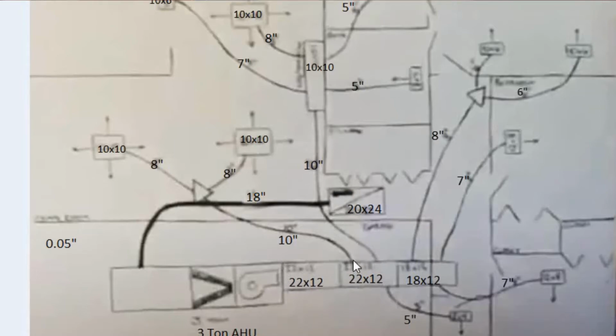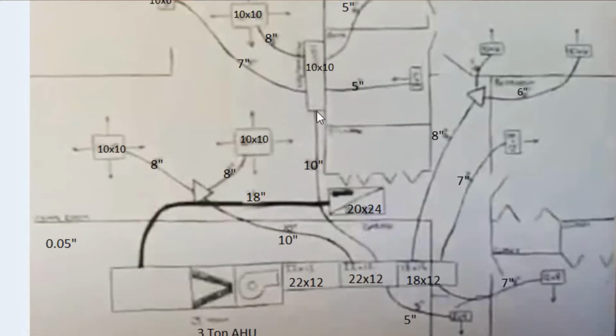Dampers, okay? If you've got dampers in the section, I don't know if this guy puts dampers in, but you should put a damper in, especially on a system like this, because these flex systems are so hard to balance. You'd almost have to have dampers in. So we're going to have a damper here. A damper will generally have a pressure drop of 0.03. We move on. What's our next thing that we're going to hit? If you have any other dampers, fire dampers, anything like that, you might add them in the equation.